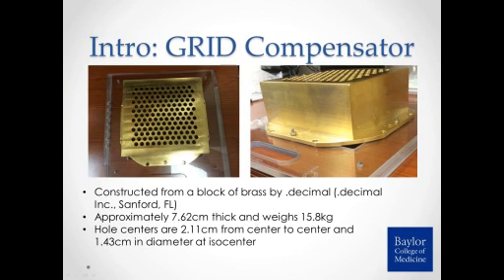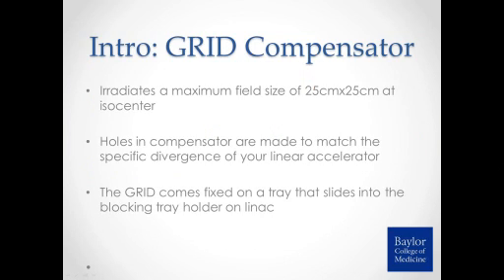The hole centers for our GRID, for our Elekta and Infinity, are about 2.1 centimeters from center to center, and about 1.4 centimeters in diameter at machine isocenter. The GRID compensator can irradiate a maximum field size of 25 by 25 at machine isocenter. The holes are made to match the specific divergence of your linear accelerator, so when you order from Dot Decimal you provide the make and model of your LINAC. The GRID comes fixed on a tray that slides directly into your blocking tray holder on your linear accelerator.